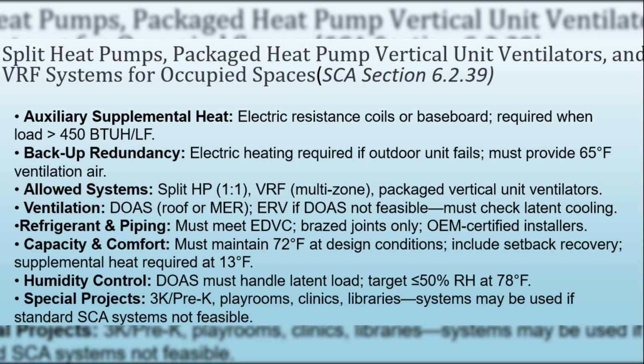This section explains how split heat pumps, vertical unit ventilators, and VRF systems can be applied in school projects. First, let's look at auxiliary supplemental heating. This is extra electric heating that kicks in when the outdoor heat pump alone can't meet the load during very cold weather. If the heating load is modest, up to 450 BTUH per linear foot, it can be handled with electric resistance coils inside the units or with baseboard heating, depending on the type of indoor unit. For larger loads above 450 BTUH per linear foot, electric baseboard heaters must be installed in the space.